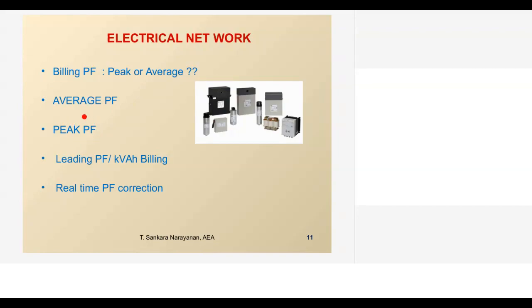If there is a variation in peak power factor, then I need to have additional compensation. Second, today some of the boards, supply companies, have gone for kVAh billing. When kVAh billing is there, leading power factor is not acceptable, because when industries are maintaining leading power factor, to a certain extent the generator can take care of it. If all are maintaining leading power factor, again the generator side has to reduce the load. So leading power factor is not acceptable today by many of the utility companies.